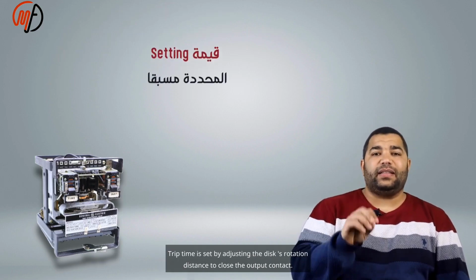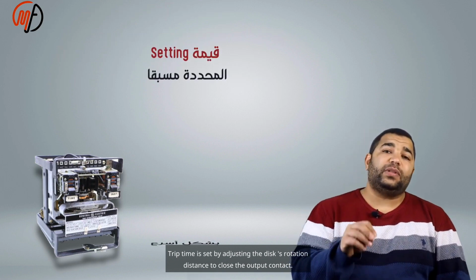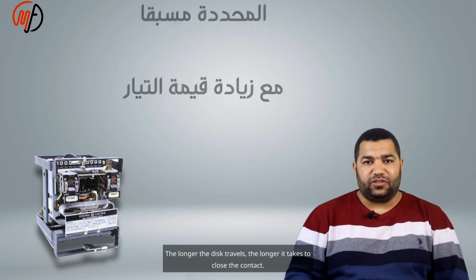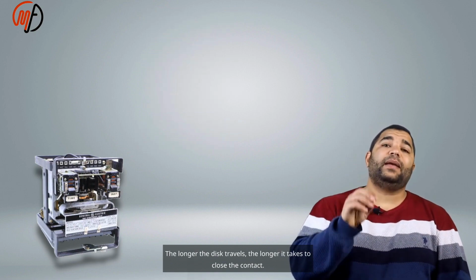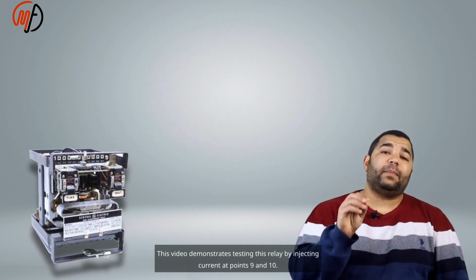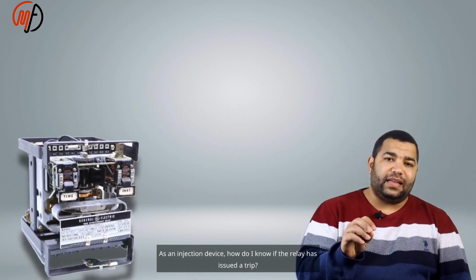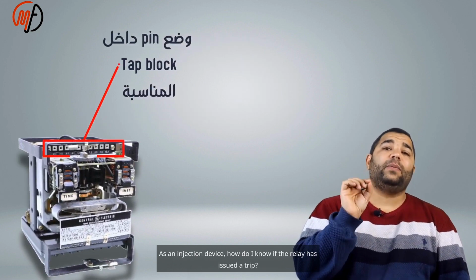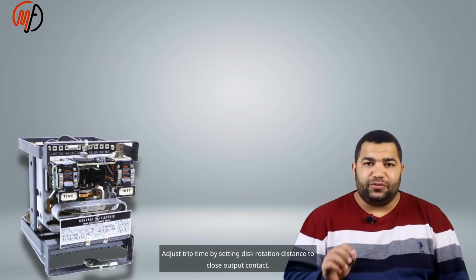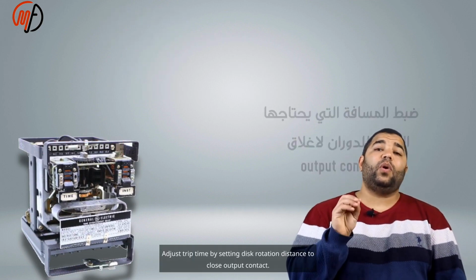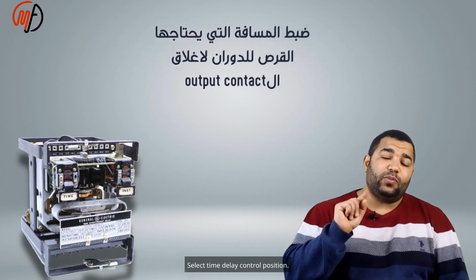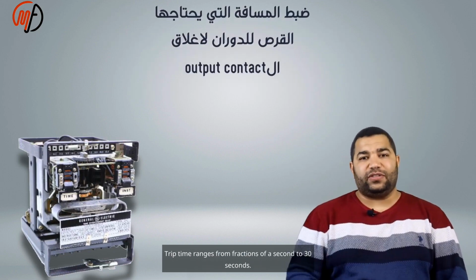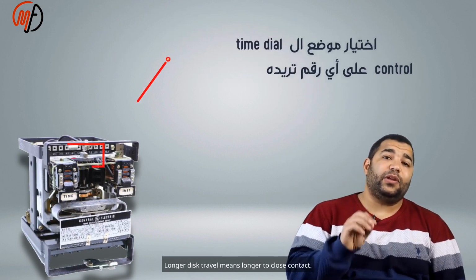Trip time is set by adjusting the disk's rotation distance to close the output contact. The longer the disk travels, the longer it takes to close the contact. This video demonstrates testing this relay by injecting current at points 9 and 10. As an injection device, how do I know if the relay has issued a trip? Select the time delay control position. Trip time ranges from fractions of a second to 30 seconds.